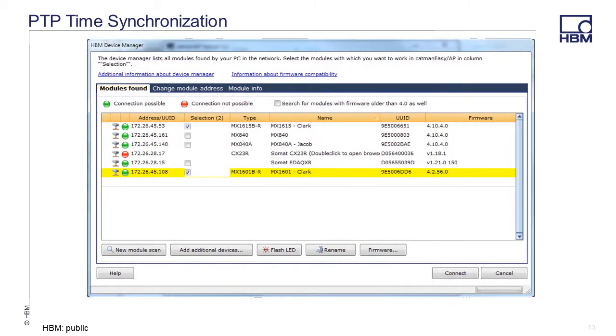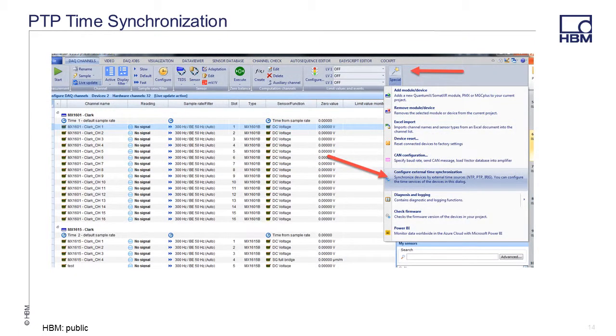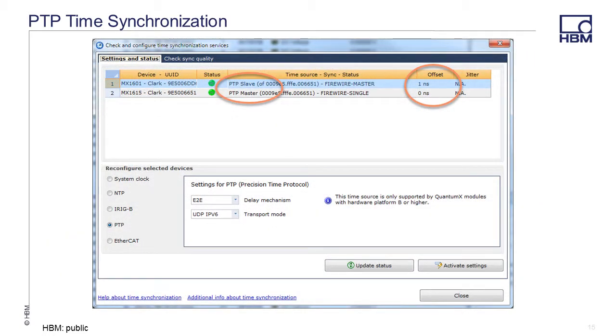Connect to the modules as before by selecting the modules you want to connect. To check the PTP time synchronization, click the drop-down menu on the Special button and select Configure External Time Synchronization. Here you can see that the MX1615 is the PTP Master and the MX1601 is the PTP Slave. The sync status is OK, so a test can be started with synchronized data.